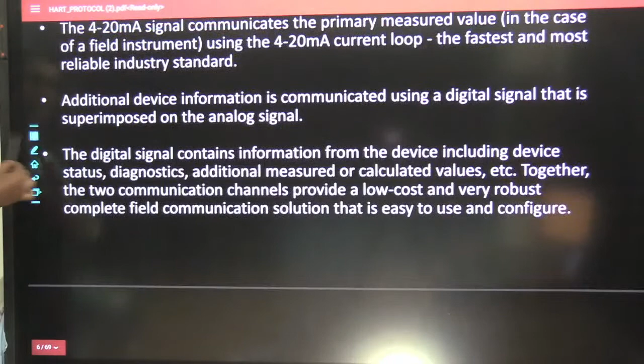That 4 to 20 milliampere signal communicates the primary measured value. Additional device information is communicated. What is additional device information? Additional device information is communicated using a digital signal that is superimposed on the analog signal. Very, very beautiful concept. Next, what is this digital signal? This is most important. What does the digital signal information contain? The digital signal information contains information from the device, including the device status.